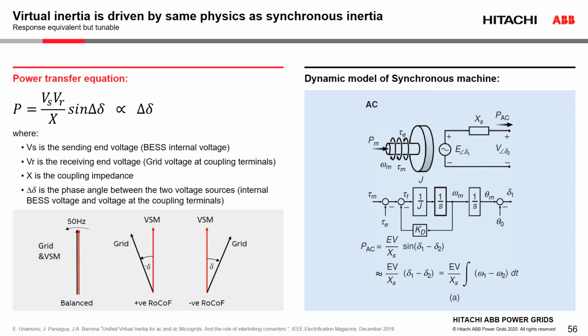Now remember, a grid-forming converter has its own voltage and frequency reference, so it has its internal speed spinning at 50 Hz. If we then go to the phasor on the far right, we have a negative rate of change of frequency event, where the grid slows down and the grid-forming converter remains at 50 Hz. So in this case, the grid actually moves away from the virtual synchronous machine that remains spinning at 50 Hz and creates this phase angle.